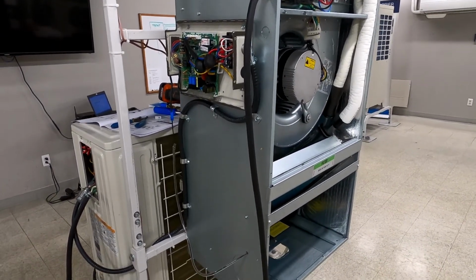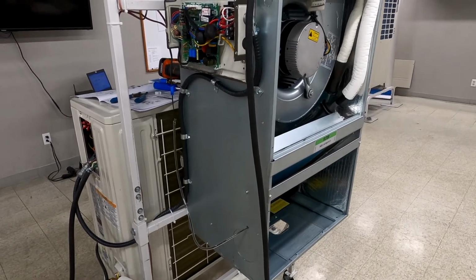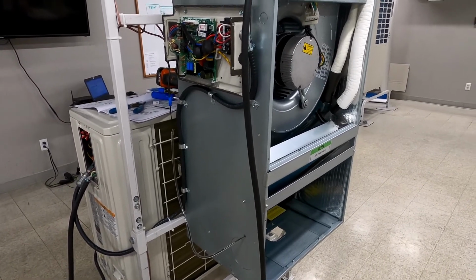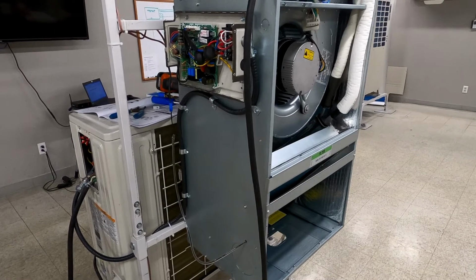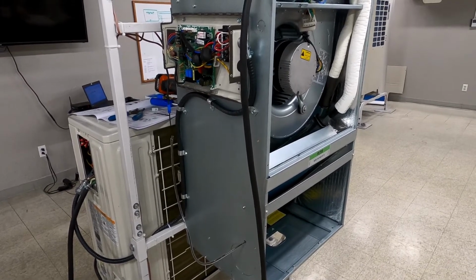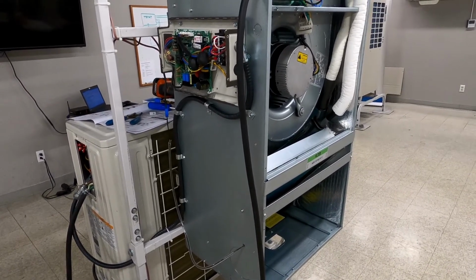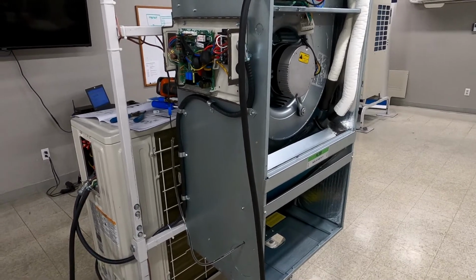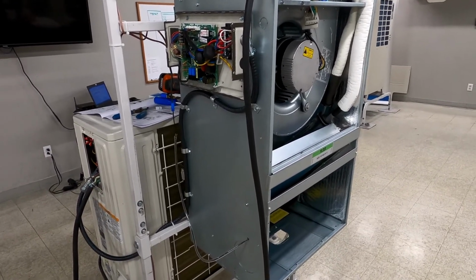So at the end of every call, the interface kit references what the return air temperature was when the thermostat is no longer calling for heating or cooling, and uses that temperature to control to for the next call for heating or cooling.